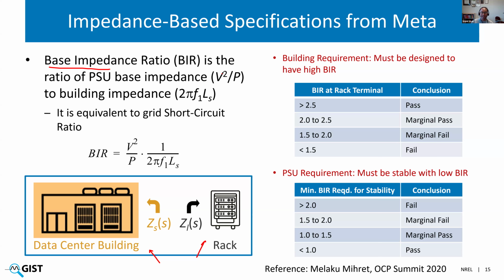The base impedance ratio is basically the ratio of the base impedance of the PSU, depending on the rating of the power supply unit, versus the actual building impedance. And the building impedance is mostly inductive in nature because of transformers as well as additional inductors that are inserted to limit fault currents. So the requirement focused on this BIR, which is again similar to SCR. And the requirement is focused on both the building side as well as the IT rack side. For the building, we want to design it to provide a high BIR or high SCR. So basically, there shouldn't be a lot of impedance within the building or within the distribution network.